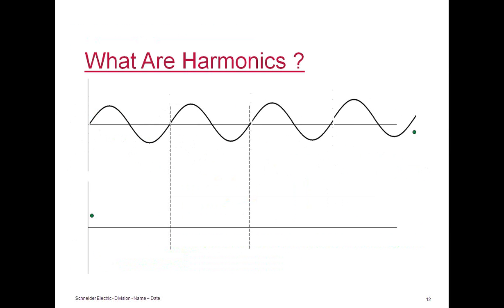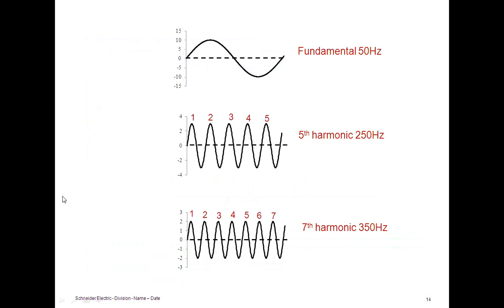Suppose we have one more AC sinusoidal frequency which has two cycles in one cycle of 50 Hz or 60 Hz. It's called the second harmonic. There are two cycles in one cycle of the fundamental, so it's called the second harmonic frequency. Similarly, if you have a pure sine wave which has 5 cycles in one cycle of 50 Hz, it's called the fifth harmonic frequency. Similarly, we have the seventh harmonic, 11th harmonic, and so forth. So a harmonic is nothing but a pure AC whose frequency is a multiple of the fundamental. When you say multiple, it has to be integral, a whole number, because we don't find non-integral harmonics in industry except in a few cases like arc furnaces and so forth.